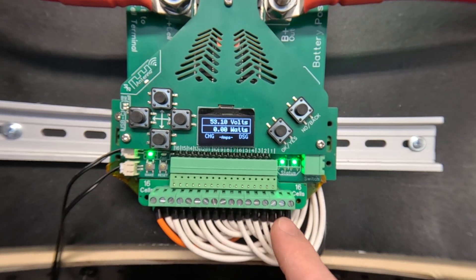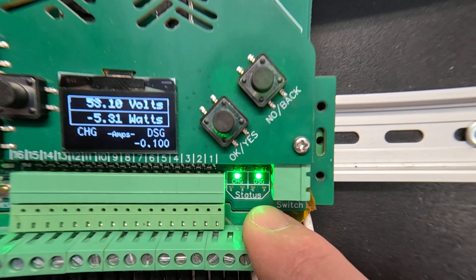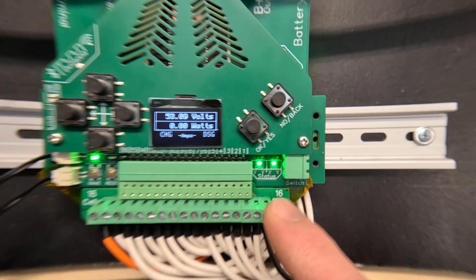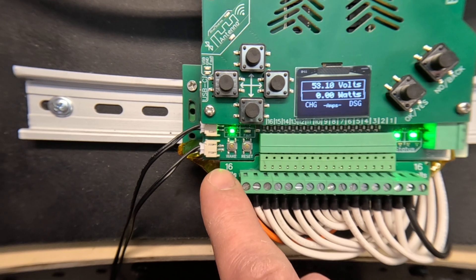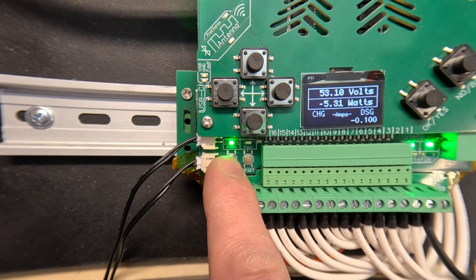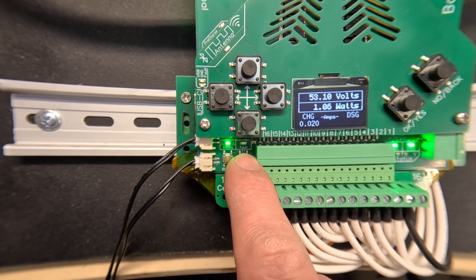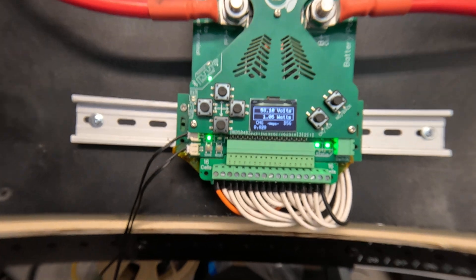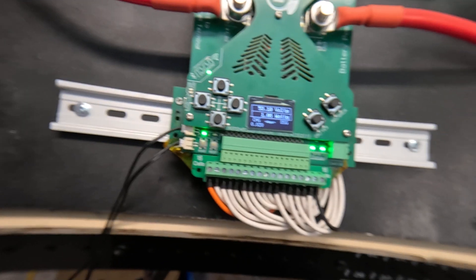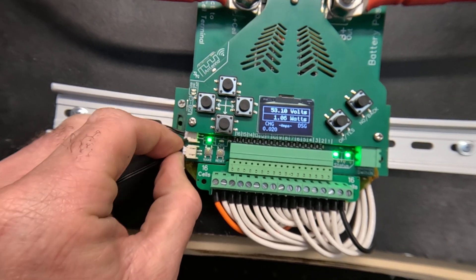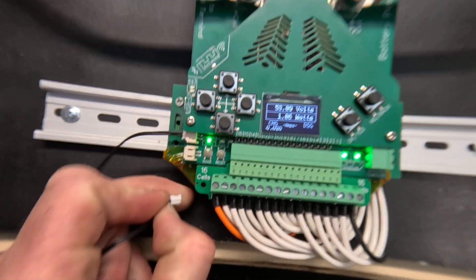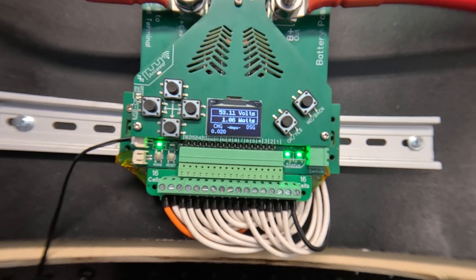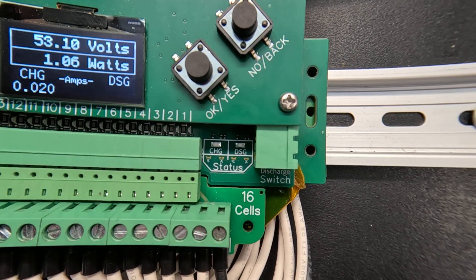Now you can see we have some indicator lights on. This is charge and discharge, that just says awake, and then there's a red light there for faults. If we had a temperature fault it would show up there. For example, if I unplug the temperature probe we'll get a low temperature fault right away and the outputs will shut off.